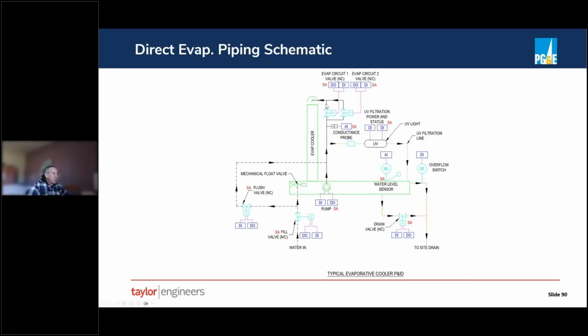You'll need some sort of conductivity control, just like a cooling tower. You need to have the ability to drain out some of that water because the conductivity will get too high, right? The concentration of solids in the water gets too high. So you need to do conductivity control. Because it's water that's being evaporated into the airstream, you can't chemically treat it typically. And one way to do treatment to mitigate biological growth is with UV filtration. So that's very common in data centers, to use UV.